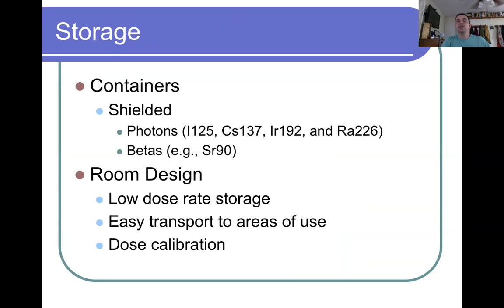So really, what dictates how these sources are safely stored is the photon energy. Most of these sources are photon emitters. There are beta sources. We don't use these as much as the low energy photon emitters. You would use them to achieve the same means of keeping that dose as local to the cancer as you can. So we're mostly dealing with photon emitters. Something like I-125, you can keep in a very thin lead lined pouch, and that will stop pretty much 100% of the radiation. Versus something like cesium, or back in the day when they were using radium, you needed inches of lead to be safely in the presence of some of these sources. So really, the energy dictates the type of shielding that will be present.